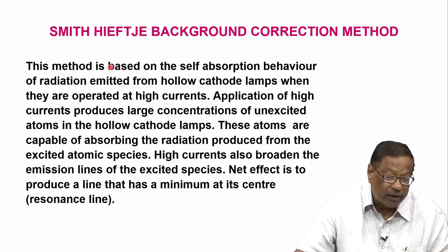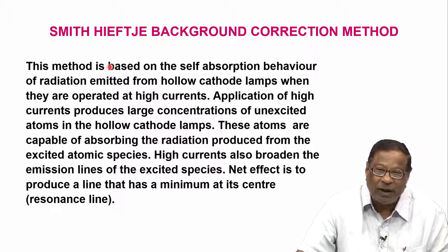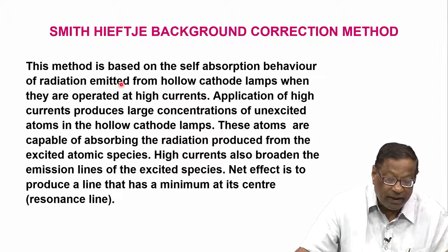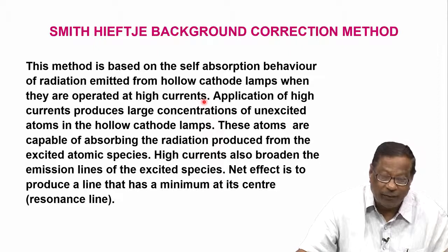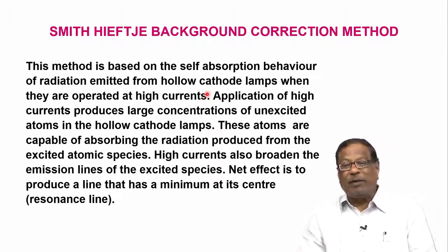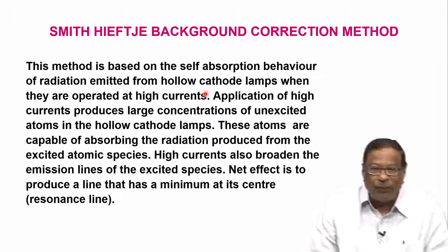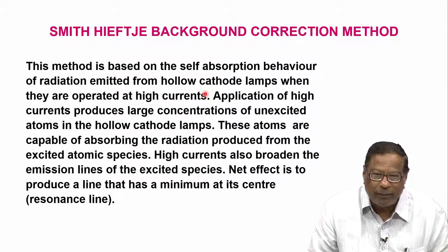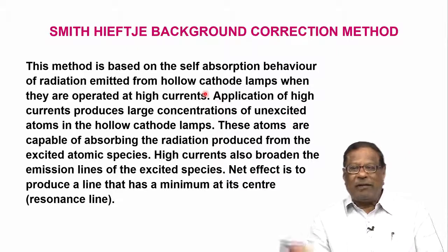So, what is the Smith-Hieftje background correction method? This method is based on the self-absorption behavior of radiation emitted from hollow cathode lamps when they are operated at high currents.